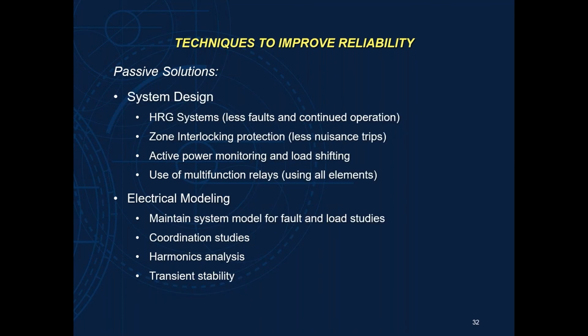System design: there are ways that we can reduce the number of faults on our electrical system by installing what's called a high resistive ground system. It virtually eliminates the chance of an outage from a ground fault. Doing things like zone interlocking protection is more to prevent nuisance trips from your protection system, okay?